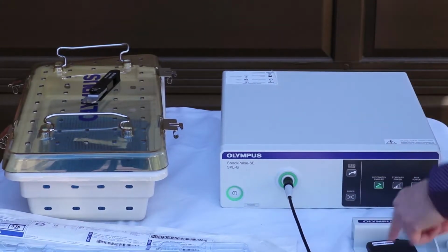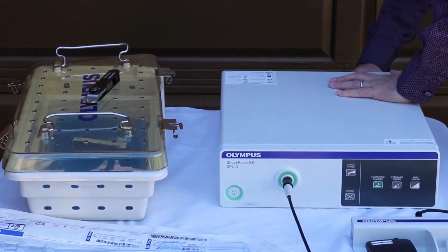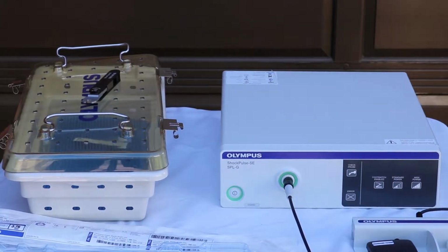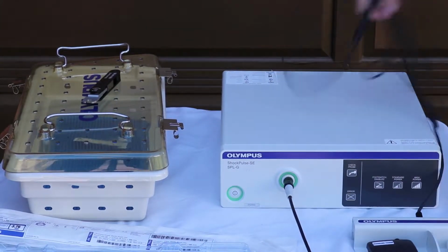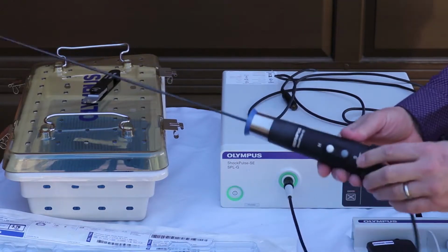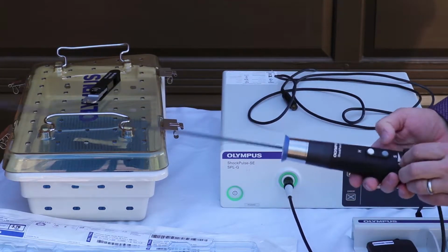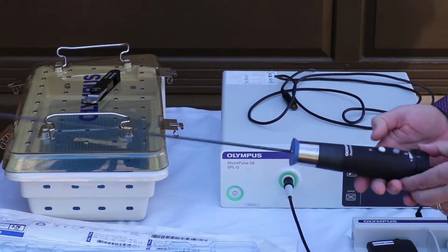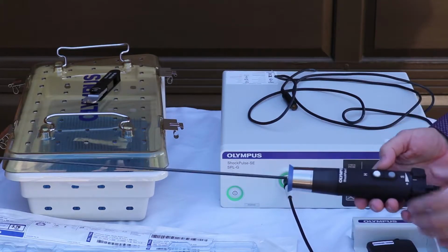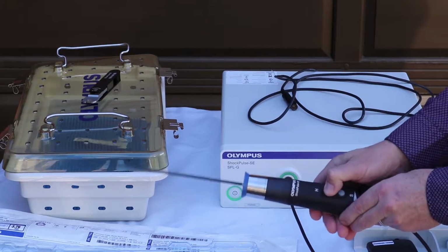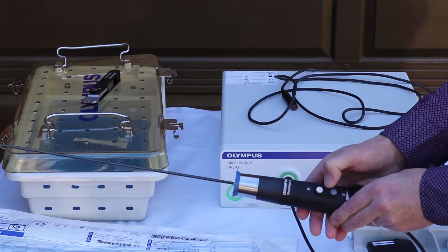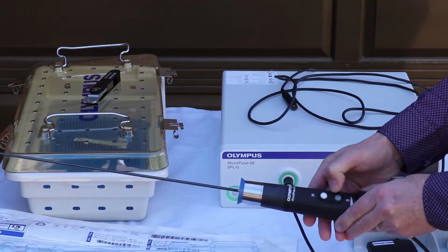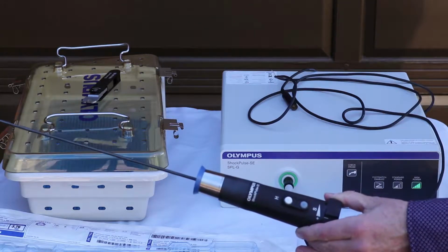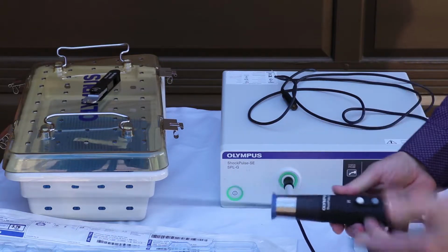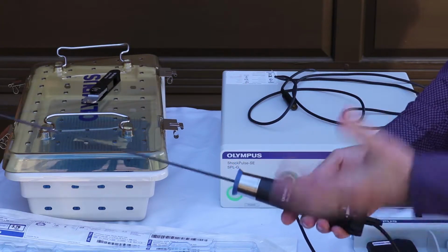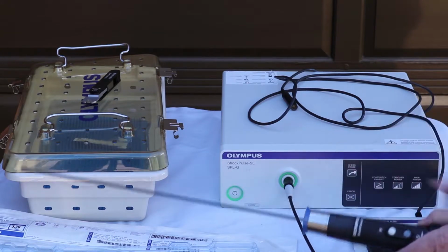The other thing that you can do if you're not using the foot switch, this is kind of a cool feature, but it can be tricky to operate, which is why I typically set it up with the foot switch. You can use the buttons here to operate the device, and if you double click it like a mouse, it'll activate and just run. So I'll show you here. There it goes. But as you can see, it took me a couple tries to get it going, so they don't work perfectly, which is why I typically use the foot switch.